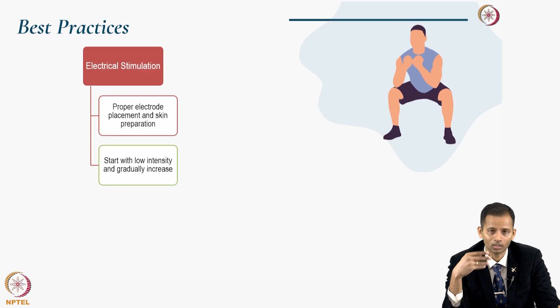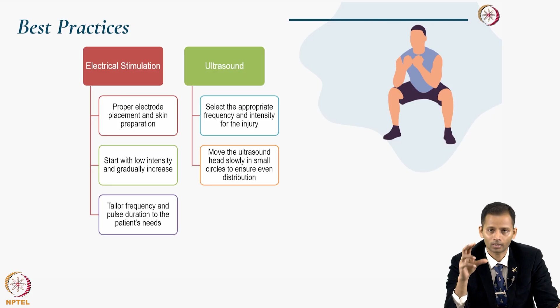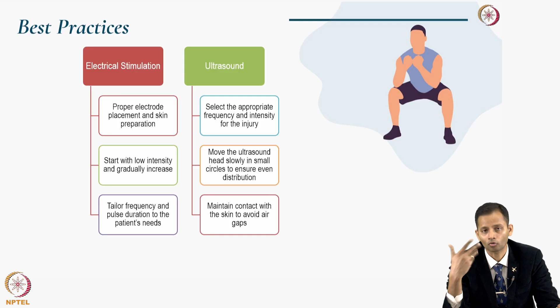With respect to ultrasound, selection of the right frequency and duration is important depending on the location of the treatment region. Move the ultrasound head slowly in a circular movement, which also causes a micro massage for even distribution. There should not be any gap between the applicator head and the skin, so it is important to have adequate gel contact. In fact, you can even add diclofenac gel, which can be used as an additional pain relieving modality called phonophoresis.